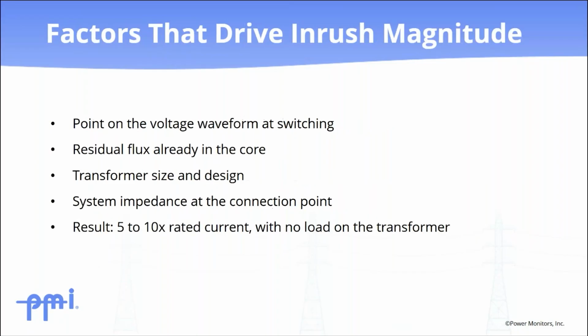There are a few factors that determine just how big and how distorted this inrush current ends up being. The point on the voltage waveform at which switching occurs, residual magnetic flux already in the transformer core, the size and design of the transformer itself, and system impedance at the point of connection. The bottom line is that the initial current during energization can hit 5 to 10 times the transformer's rated current, even though the transformer isn't actually supplying load yet. That current waveform is highly distorted and it decays gradually as the core flux stabilizes back to normal operation.